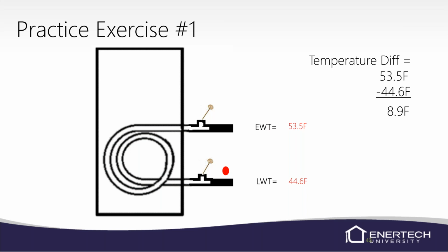So in this example, if we've got 53-degree entering water temperature and 44-degree leaving water temperature, what mode of operation are we in? Well, we're in heating mode, because we're extracting heat from the water and putting it into the refrigerant in that heat exchanger, in that coax that's right there in that picture. If you're in heating mode, your entering water temperature will always be higher than your leaving water temperature. And in cooling mode, your entering water temperature will be lower than your leaving water temperature. So in this example, we have an 8.9 degree temperature difference. Sounds pretty good.